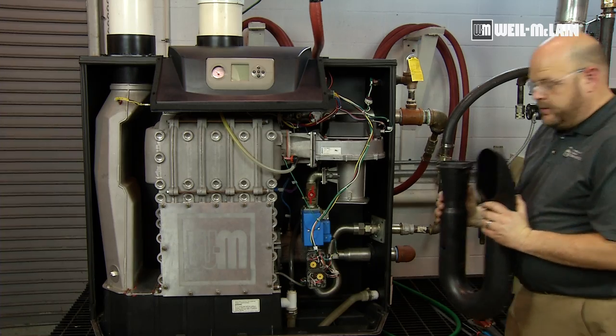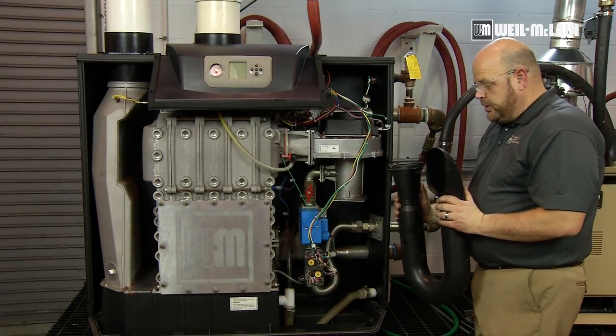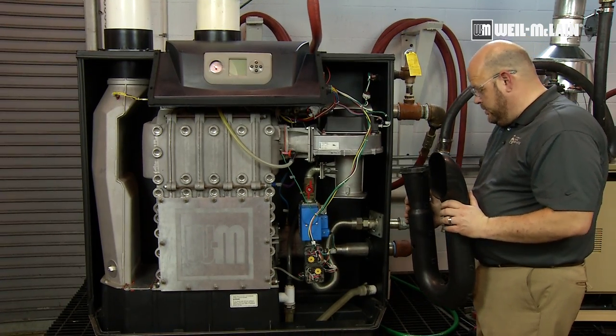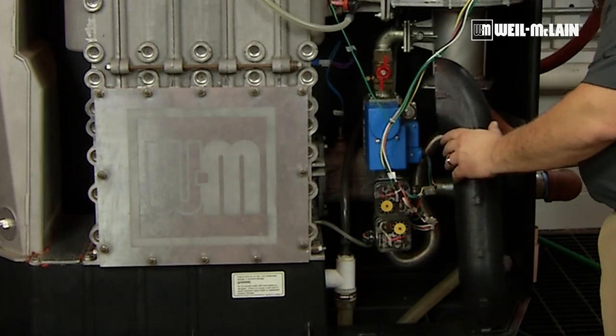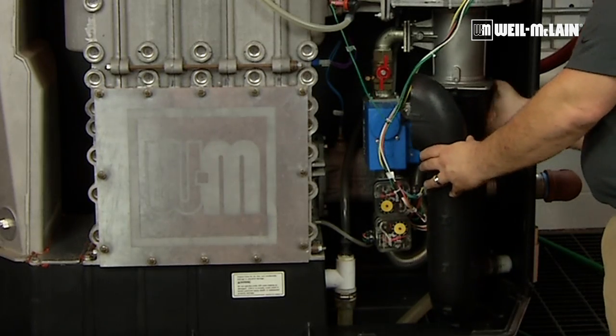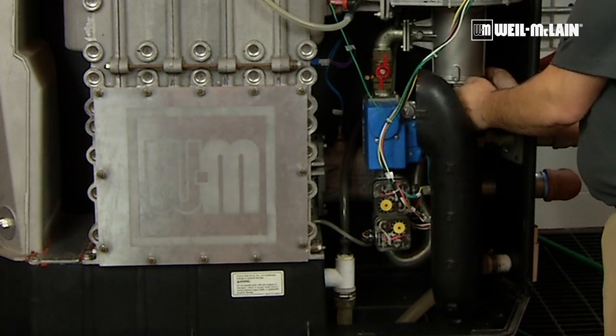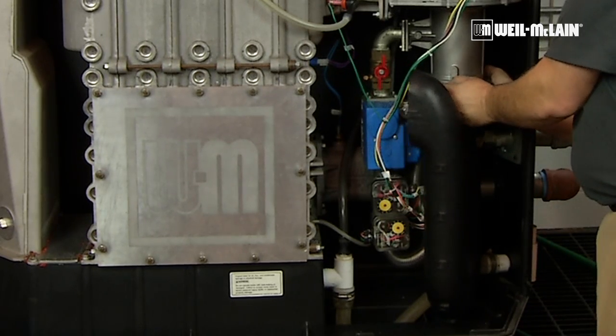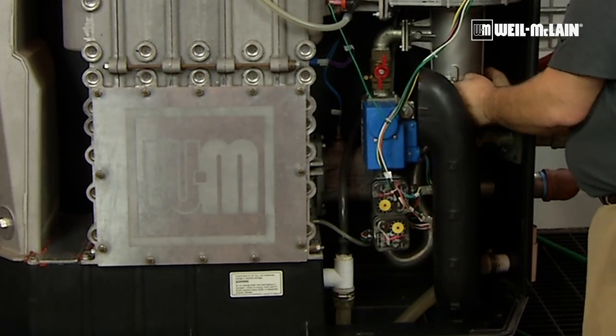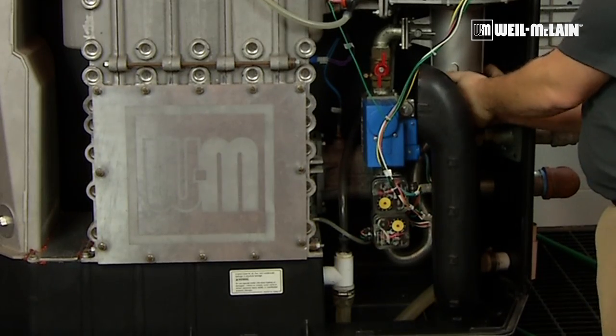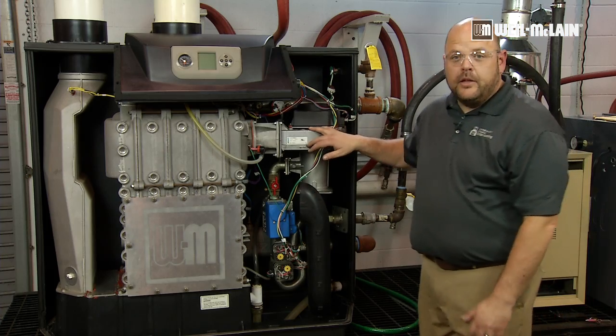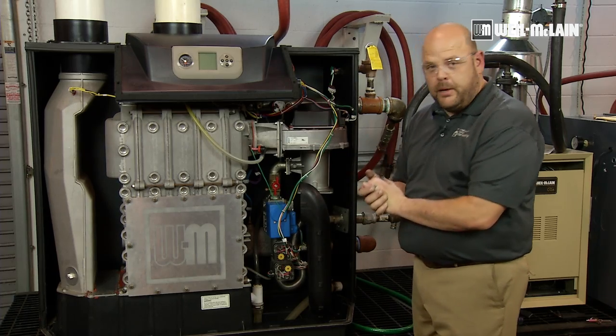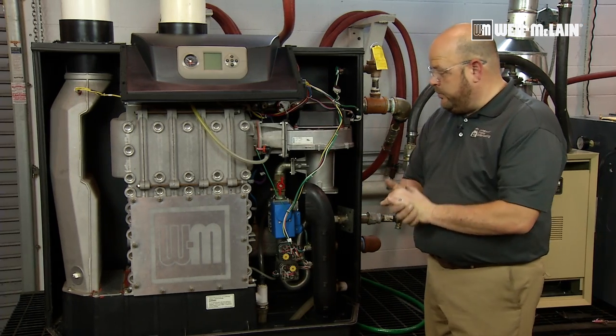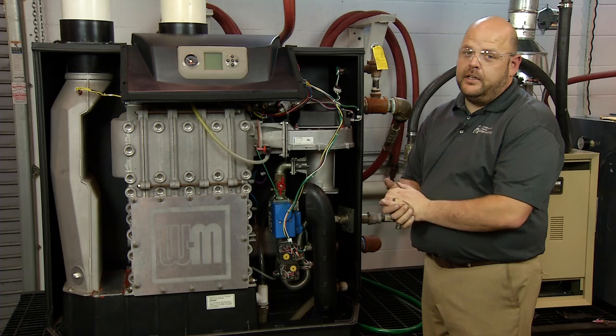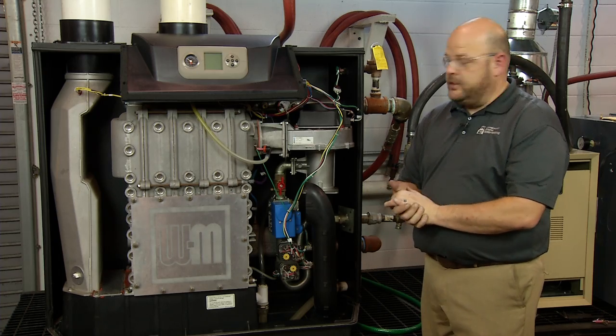We can grab our venturi air silencer, bring that into the bottom of the venturi, and snap into place. Now that the boiler's reassembled, we're going to want to follow your manual and set the high and low fire combustions to spec.